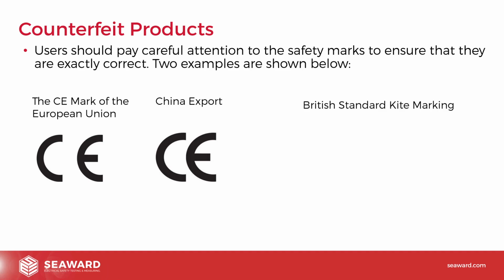Users should pay careful attention to the safety marks to ensure that they are exactly correct. Two examples are shown below. So again, we've got the European CE mark, which we'll be very familiar with, and the not so reputable China export mark, which is effectively a clone of that mark, or a facsimile of that mark, a counterfeit version of that mark. And again, that doesn't really mean anything. It doesn't mean it complies with the CE marking requirements. It just means that somebody's printed a C and an E on there from that side of things. So just be careful of the way it's laid out.